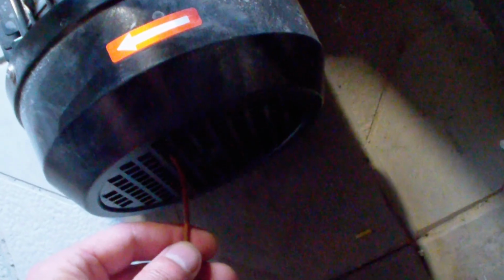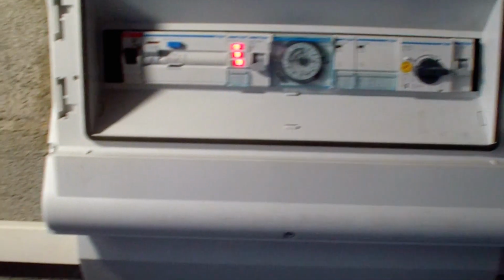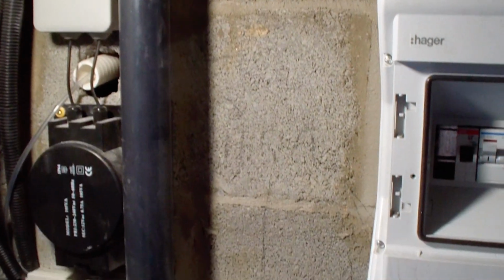We swapped 2 wires and now we are checking the direction of the pump's rotation again. Carefully insert a piece of wire into the cooling cover of the electric motor, and turn it on for a short time. Now the pump is rotating in the correct direction. Everything is great. The control panel is ready. All cables are laid and connected.